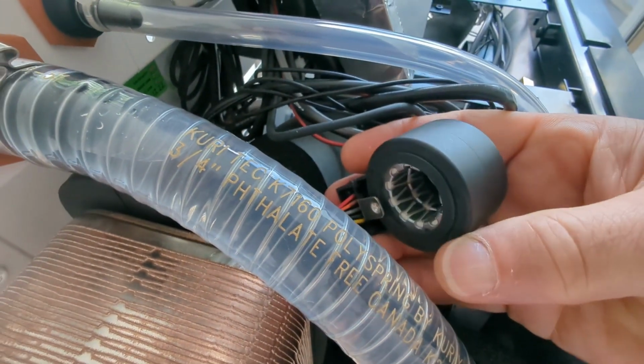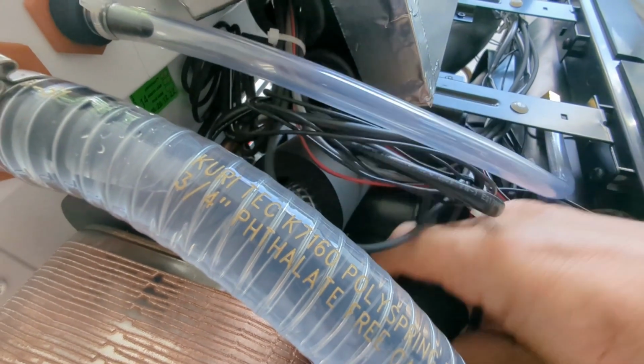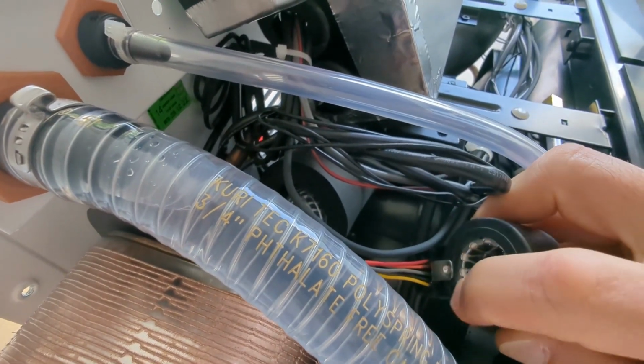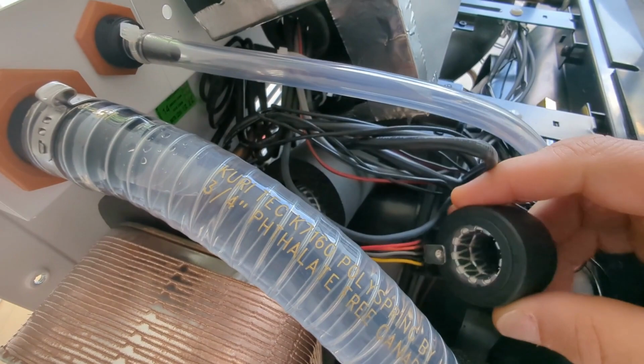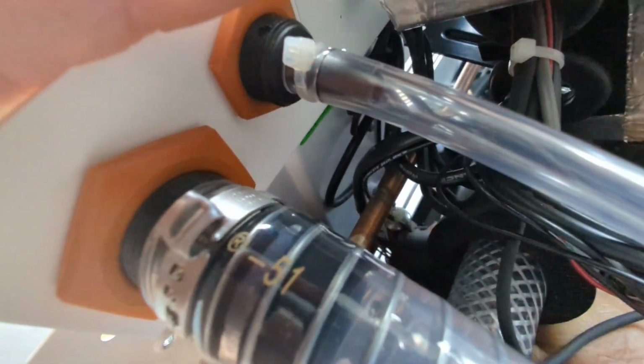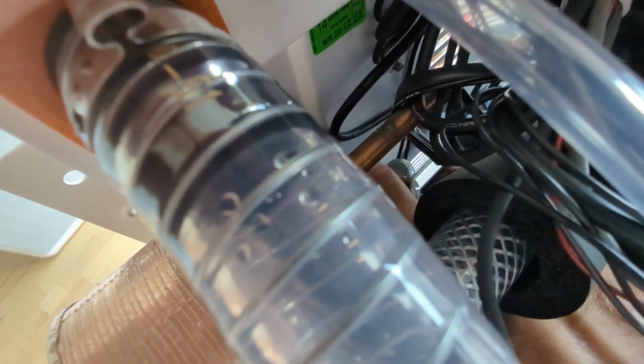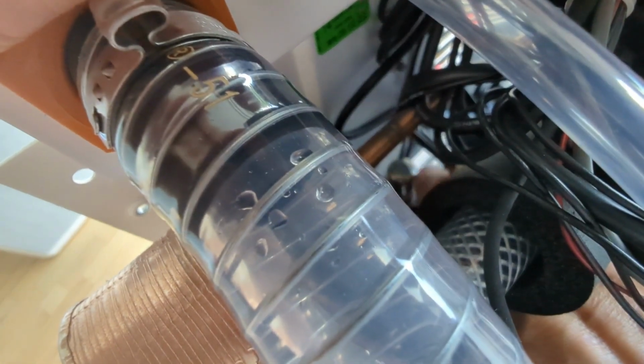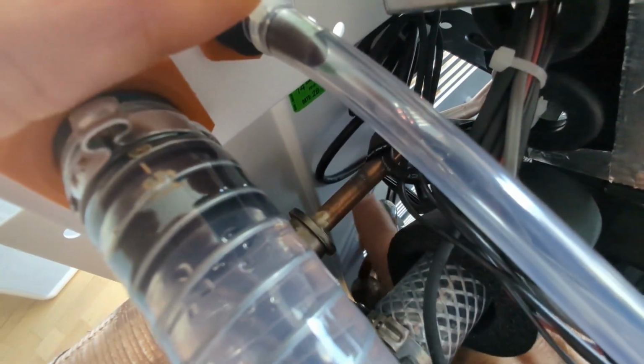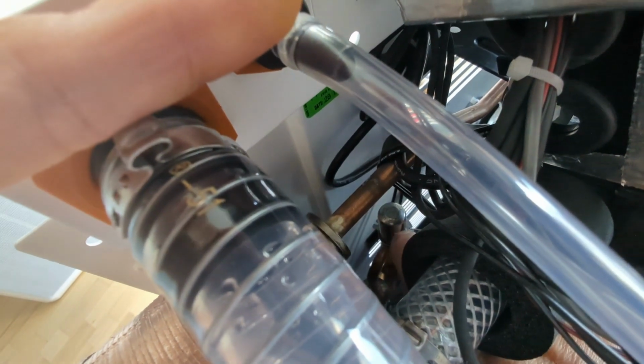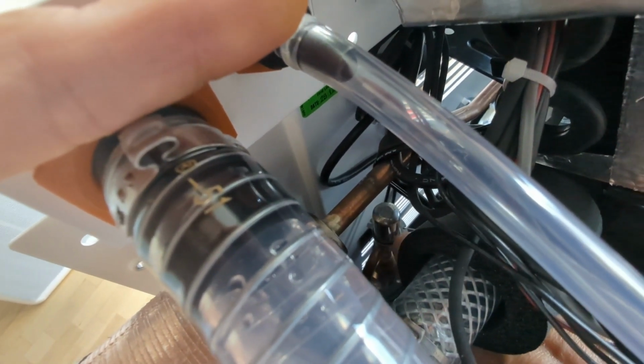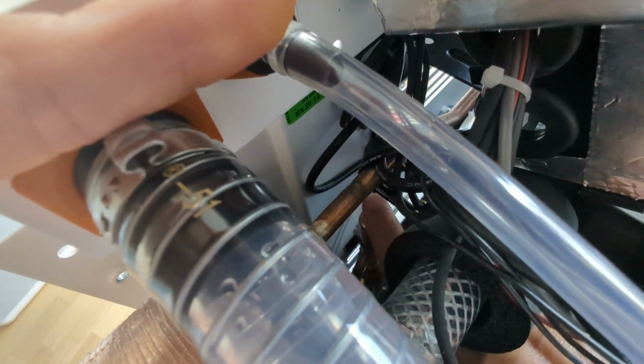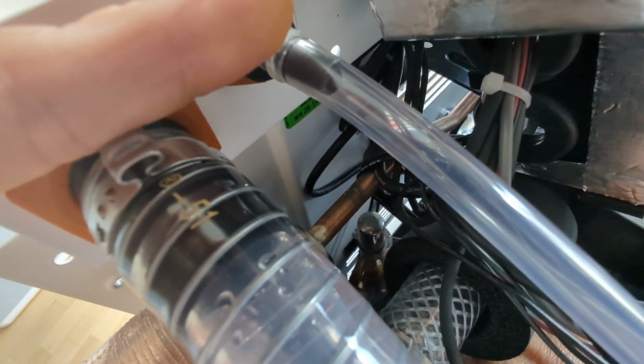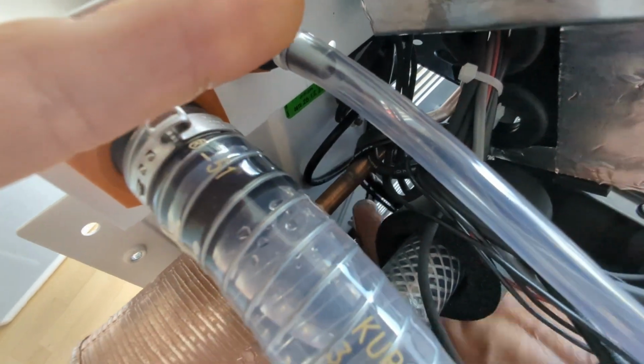The controller energizes these coils in series, and by doing that, it makes a magnetic field that sort of rotates around through this donut. And then this donut fits on top of a little capsule that's sealed into the refrigerant system. And this is it, if you can see it, right here. And in there, there's a magnet. And so as those coils energize, the magnet in here turns, and that is turning the needle valve, making it go up and down and opening and closing the valve. So cool that this is completely sealed because the magnet is going through this head here.